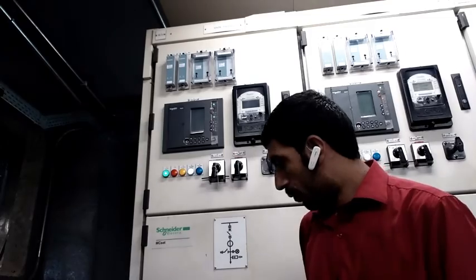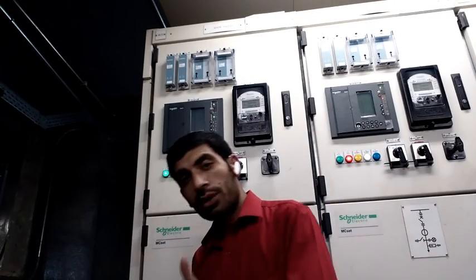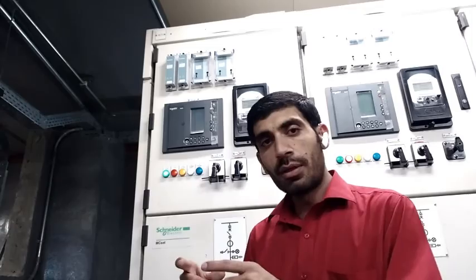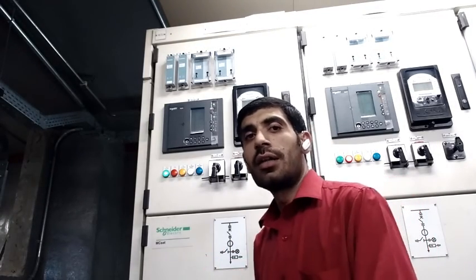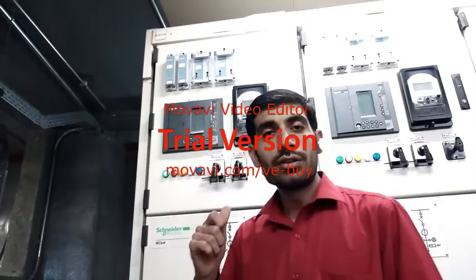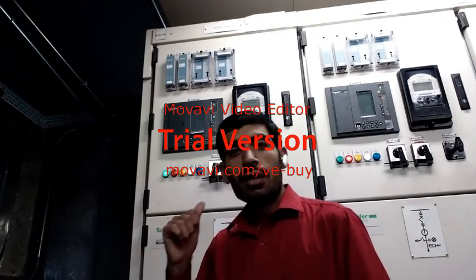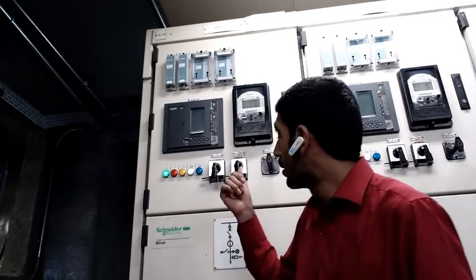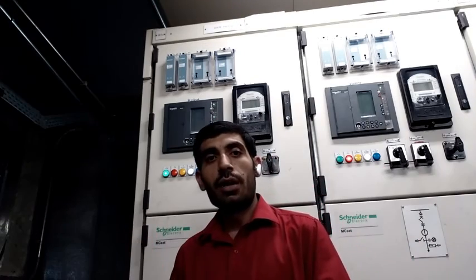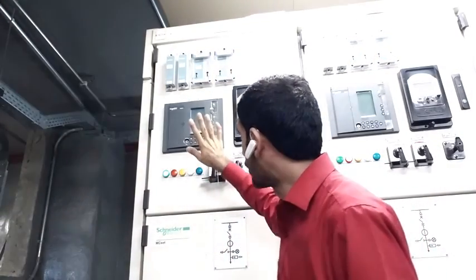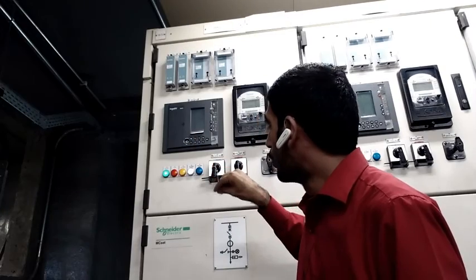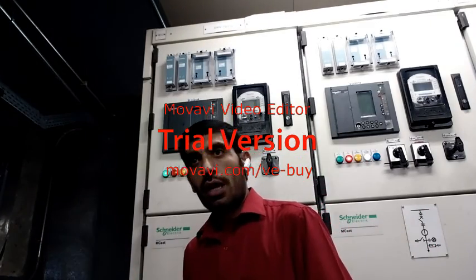And for earth fault, we use a round type CT on the output cable. We put a round type CT inside the output cable for earth fault, and the rated value of the earth fault CT is 100 by 1 amps. If my primary side is 100 amps, the secondary side should be 1 amp. And I select in this relay my rated value as 10 amps, and my secondary side will become 0.1 amps.